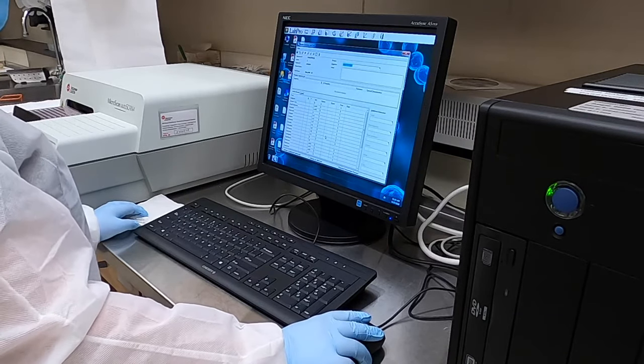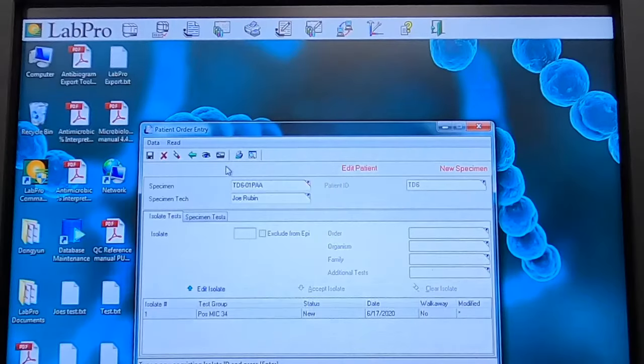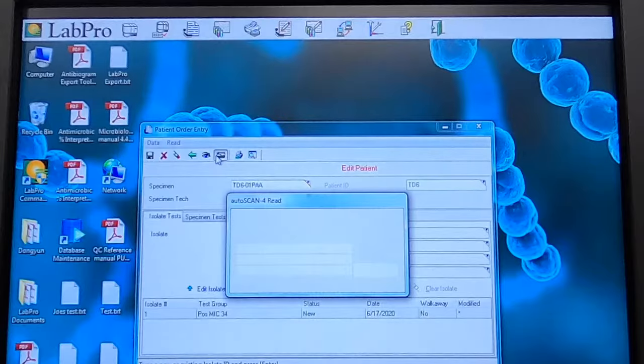It determines whether or not there's growth in each well, determines the MIC for each drug, and then categorically interprets those MICs using the CLSI guidelines based on the species ID that was input into the form.